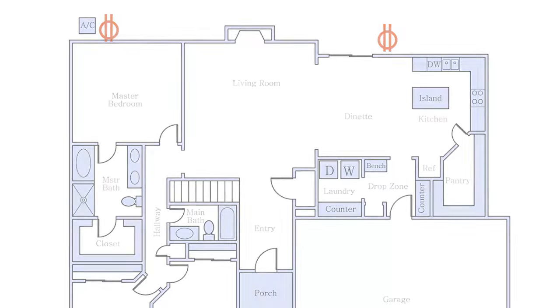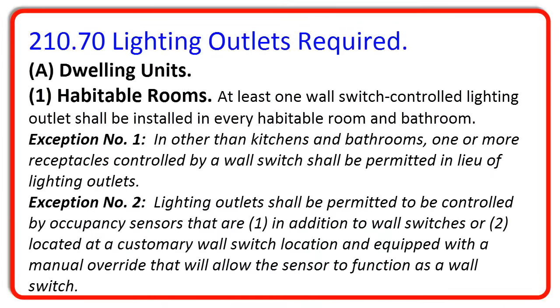Moving into Article 210.70, which is the last article we will deal with in Article 210, we see that it's required to have a wall switch controlled lighting outlet in every habitable room and each bathroom. There are exceptions to this code, and in other than kitchens and bathrooms, one or more receptacles controlled by a wall switch shall be permitted instead of an actual light fixture. Which means in kitchens and bathrooms, we have to have a light fixture that's controlled by a wall switch.